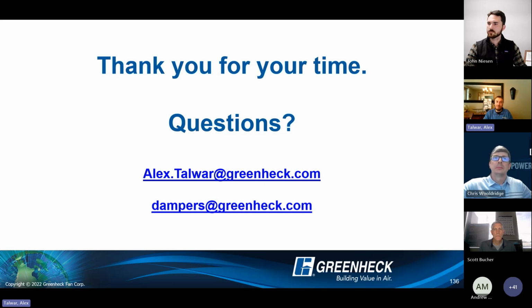Having our dedicated test labs allows us to really hone in the pressure drop performance on these products. So if you're looking at a Greenheck product, chances are you're getting the best pressure drop in the industry in terms of damper performance. And we do offer some engineering trips up to the factory, and you can see Alex in person potentially. In all his glory, and there's some fantastic damper demos, and you can actually test some of the fusible link opening and closing, and it's a great way to wake people up at 8 a.m. when you hear one of those curtain fire dampers slam shut. And there's also some great pressure drop demos too, when you're just even looking at a regular volume or balancing damper.